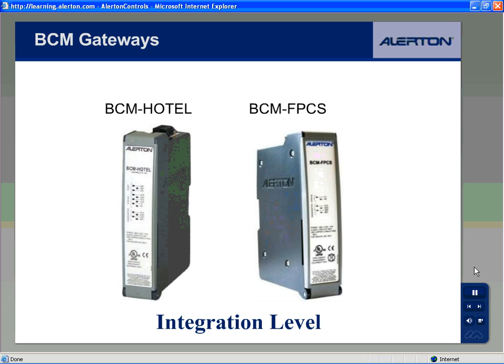The BCM FPCS can serve as a gateway between Siemens P1 protocol network devices and Alerton's Envision for BACtalk software and BACnet system. Host automation features such as schedules, trend logs, alarms, optimum start, zones, demand limiting, and tenant activity. Run DDC sequences for connected devices.